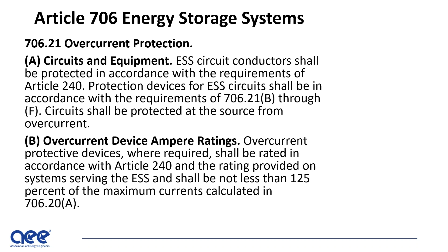If you go to B, where you're talking about overcurrent device ampere ratings, it says the overcurrent protective device, where required, shall be rated in accordance with Article 240, and the rating provided on the system serving the energy storage system shall not be less than 125%. Again, what we're seeing with all these requirements is making sure that you have a safe installation, it's properly protected, and trying to prevent situations where you're going to have fire, like what we saw in the first couple of slides.